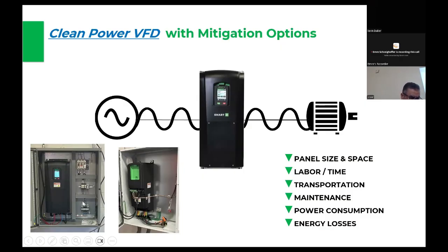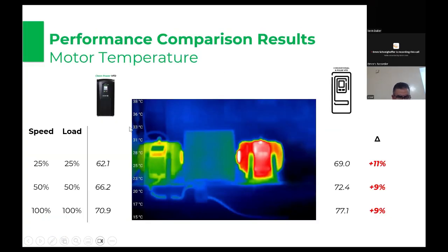And so your footprint's now less, your costs go down for your packages, of course, transport, maintenance, and your energy consumption goes down. So now, with testing, we can show you that the motors run cooler. So here's an example of a motor on our drive and a motor on a competitor's drive. Somewhere in Northern Europe is where this one comes from. You'd all know the name. And at different loads and different speeds, you can see the delta differences in operating temperature. If you're running data centers, if you can get all those motors to run at 10% less, who wouldn't love that? That's a huge impact. Of course, extending the life of the motor as well.